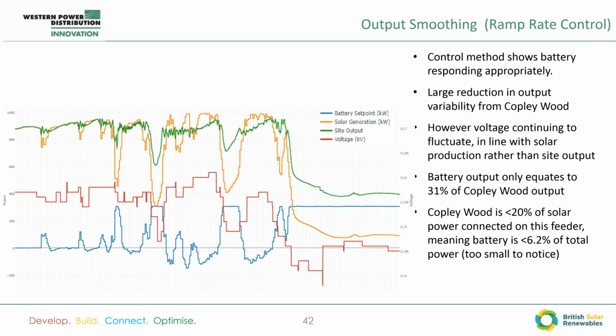So here we have ramp rate control. And you can see the orange being the solar generation. There's large dips in generation at a variety of points, and yet the output level of the park is maintained fairly well, specifically towards the middle of the day there, where the output is maintained as an average of peaks and troughs of the park. The larger troughs, again, the battery was too small to be able to fill in entirely. This is due to the sizing of the battery rather than an actual problem with the control system.